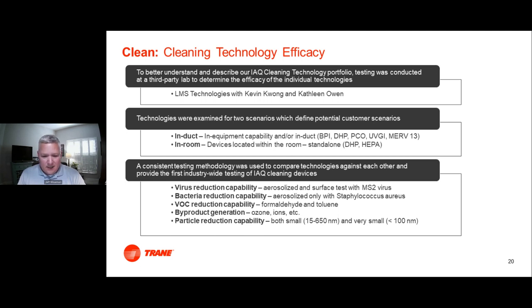the results. And the intent of our testing was not to get absolute performance. What we really wanted to do was to get back-to-back comparisons of different technologies on different factors. Really two types of equipment we looked at. One was in-duct, so think filtration and other equipment that would be in an air handler or in a duct. And the second group of technologies were in-room technologies, so in-room HEPA filters and bipolar ionization, which claims to react in the space, and technologies like that.